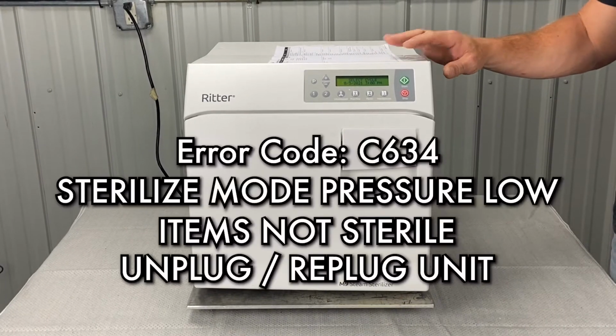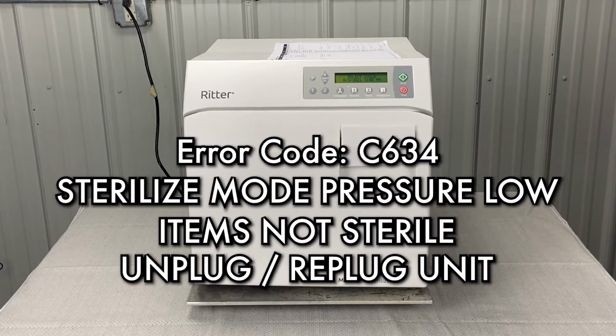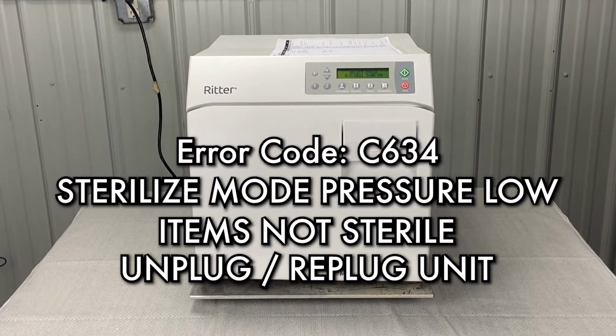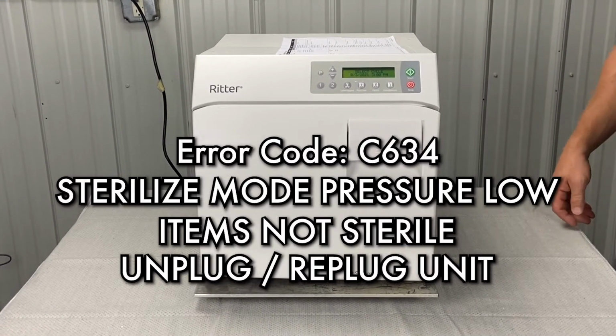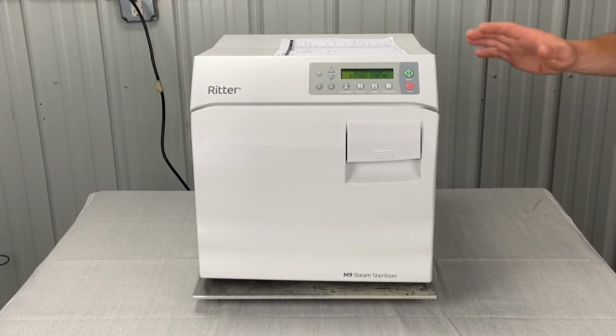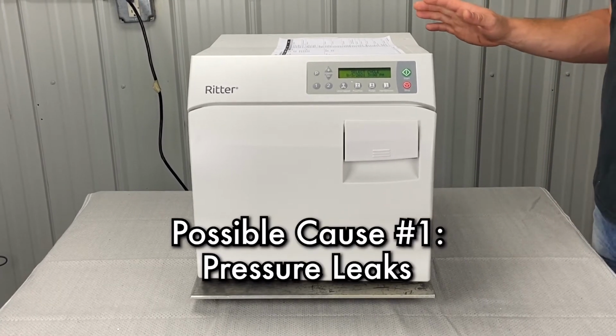Charlie 634 error code, sterilizer mode, pressure low. Items not sterile, unplug, replug. So we're gonna, this indicates pressure leaks.